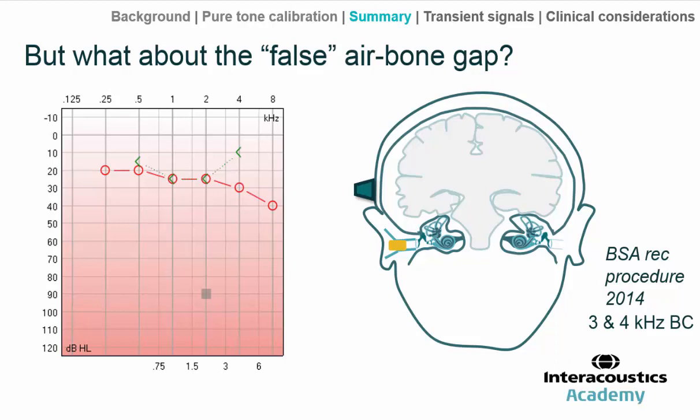Advice has been that these excessive air-bone gaps isolated to the high frequencies and hard to explain clinically may in fact be caused by airborne radiation from the bone vibrator, which can propagate down the ear canal and then be heard by the air-conducted route. This is thought to be a particular problem at 3 and 4 kHz. The advice has been to plug the ear canal with a piece of foam. But what can commonly happen is that once the ear is plugged and one follows these procedures, quite frequently it doesn't seem to have much of an effect at all.